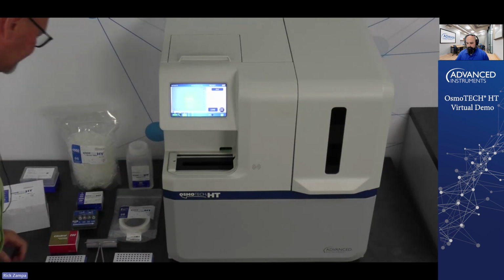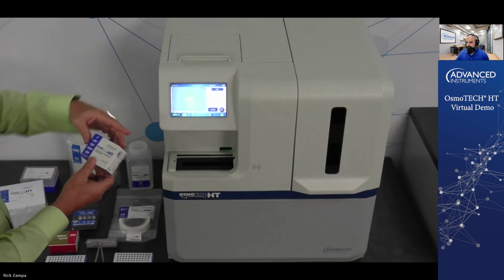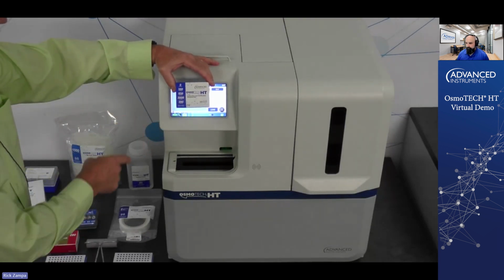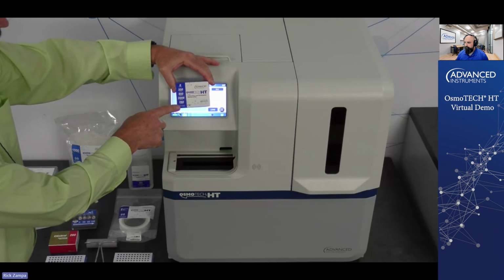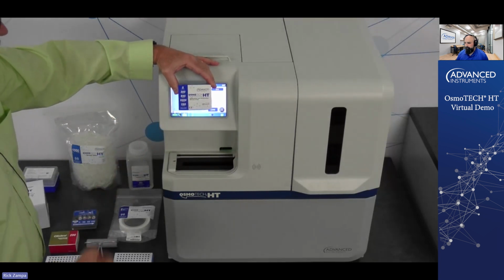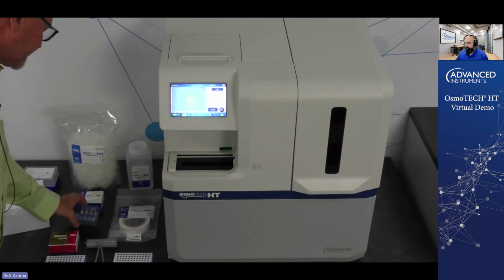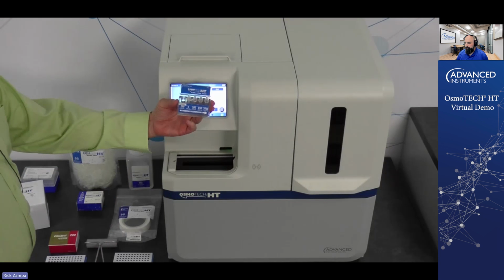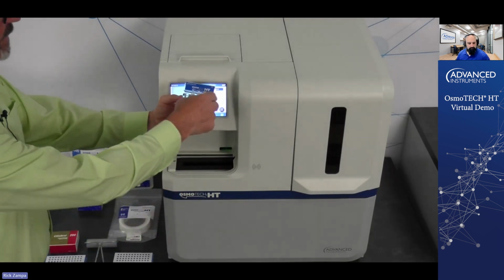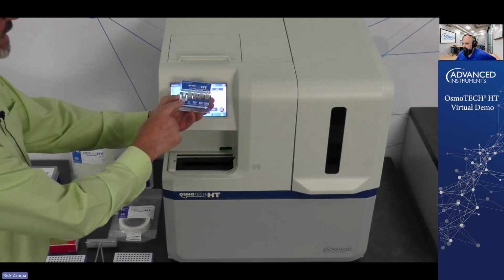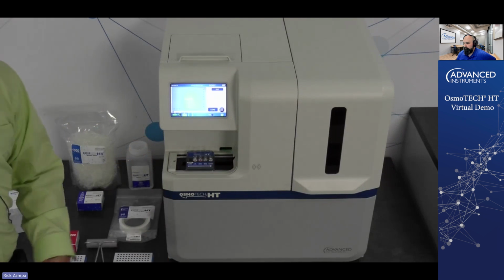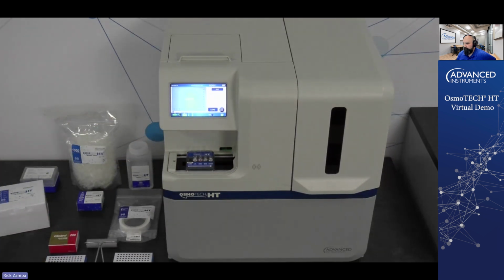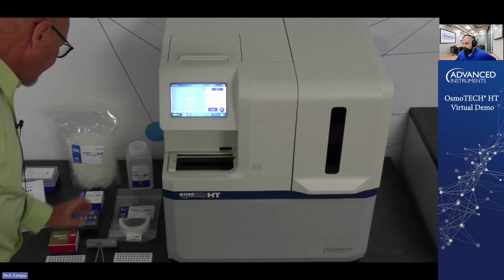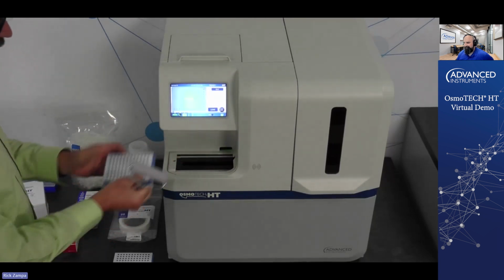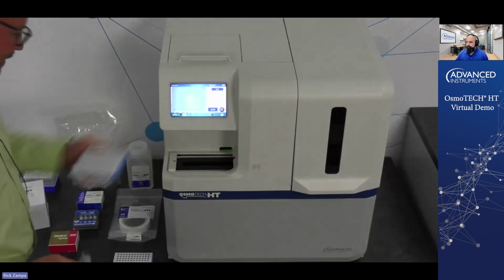That's also good for 1,000 tests. Finally, we have our calibration set and verification set here. You have your calibrators, 2 of each of the calibrators and 2 of your 290 reference solution, which allows you to run the calibrations on the instrument from one package as opposed to multiple packages. Also, what comes with the instrument is the calibration and verification plate. It allows you to load your calibrators and your verification standard into the plate. You load that onto the instrument like so, push the calibration button, and it allows you to calibrate the instrument and walk away. So that is the consumables that come with the instrument. You also get a little roller here, which can be used to make sure you've sealed the plate with the evaporation cover.